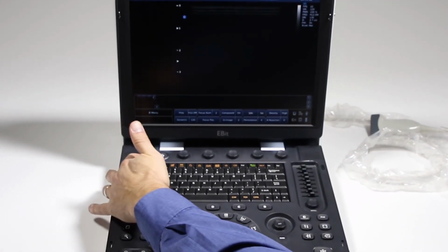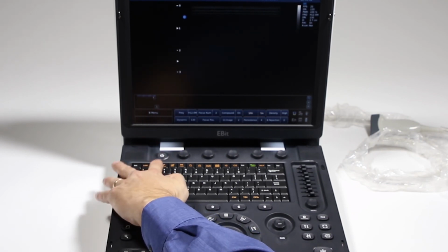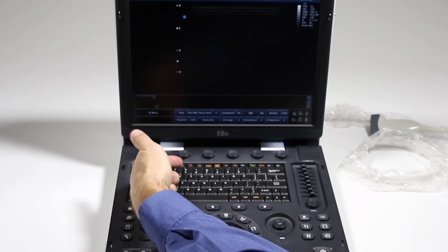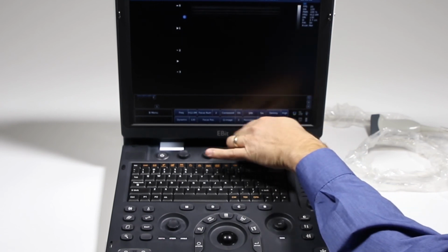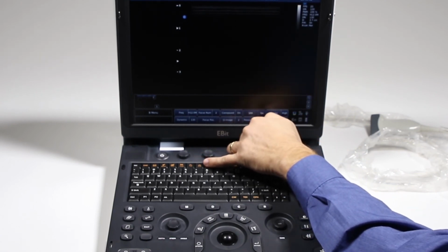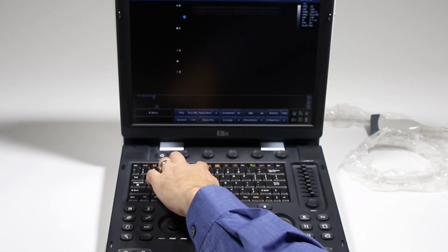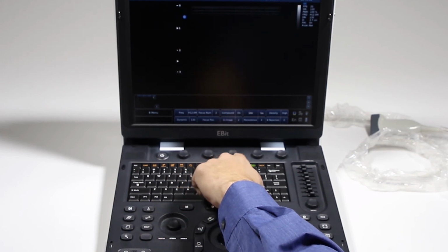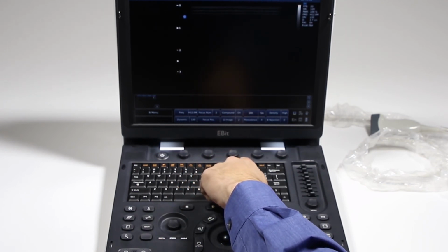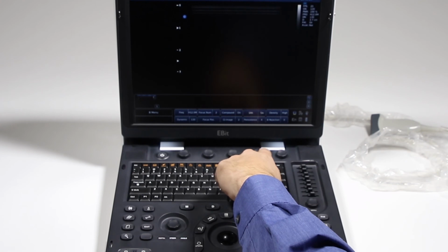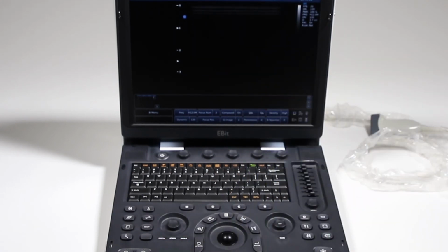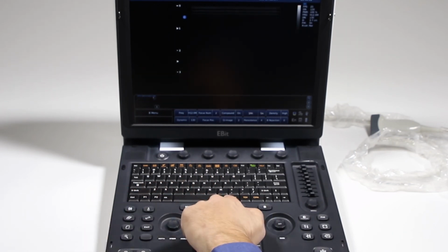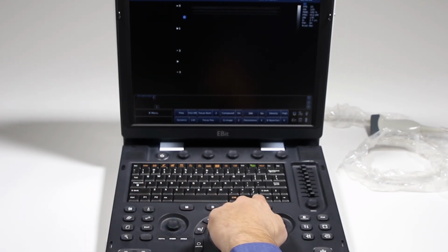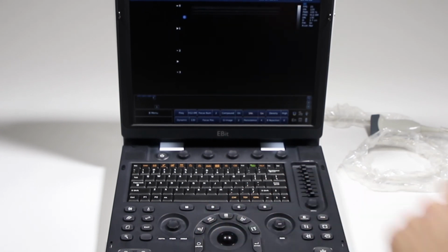Across the top, we have keys for ending the exam, body markers, arrow pointers, comments, clear, biopsy. This is for a single screen, dual screen, quad screen, your volume controls for Doppler, an assignable F12 key, and the help menu is not active at this time, but you do have this video and the user manual to go by. The rest of the keyboard is standard, but if you want CW Doppler, or tissue Doppler, or color power angio, you can click on those here.